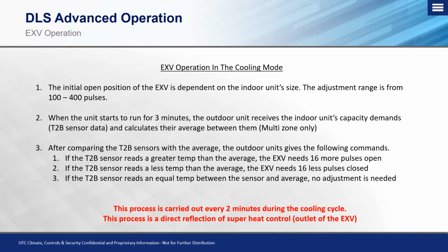So after comparing those T2B sensors with the average, the outdoor unit will give the following commands. If that T2B sensor reads a greater temperature than the average, remember the average generated for once it starts running for 3 minutes, it now has that average. If that temperature sensor reads greater than the average, the EXV will need 16 more pulses open. And this is how we're going to start controlling refrigerant flow to the indoor unit based off of temperature and that average generated for that first 3 minutes of runtime. If the T2B sensor reads less than that average, the EXV needs 16 pulses closed.